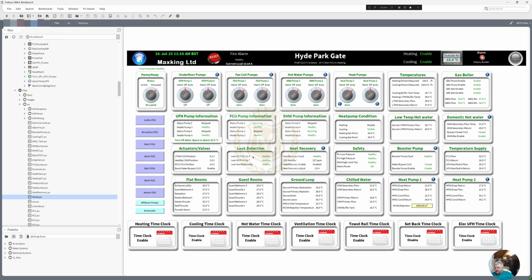Let me go back to the main home page. So if outside air is 23.3, if outside air is below 10, then fan coils are in heating. That's the only time the fan coils go into heating. There's our current load. We're at 23.4 outside at the moment, and we've got the actuators and the different temperatures here.